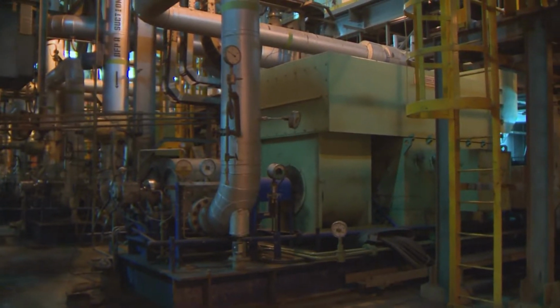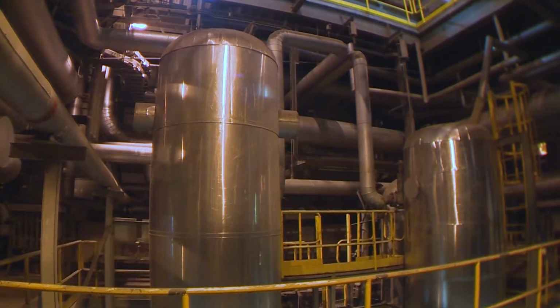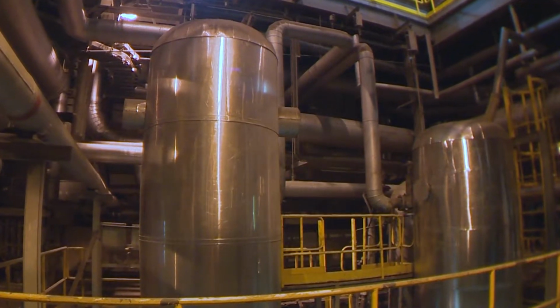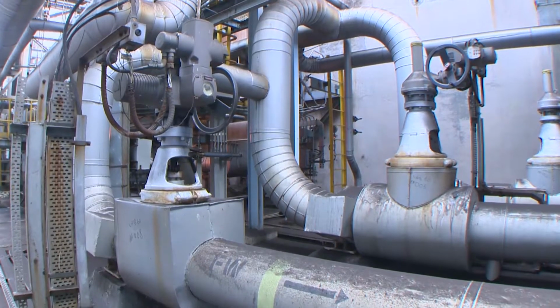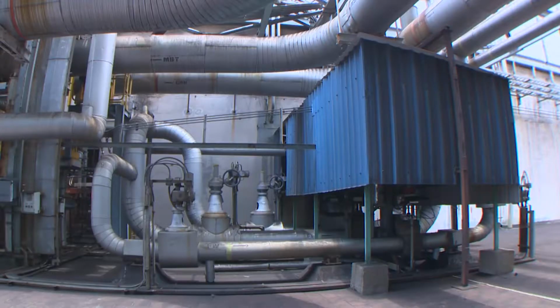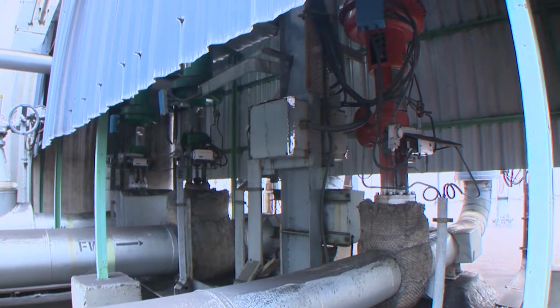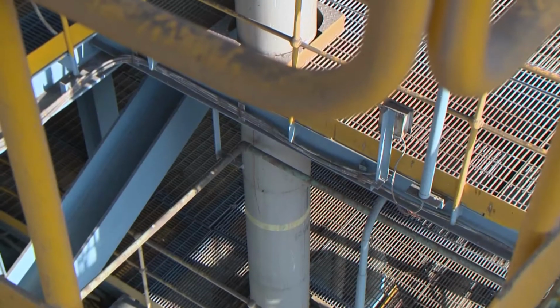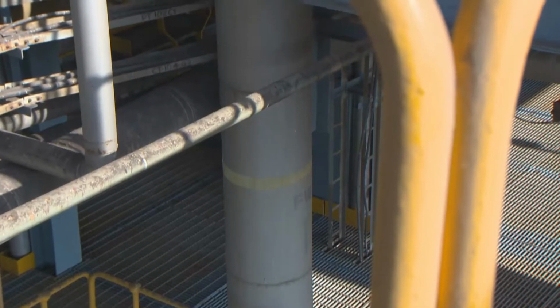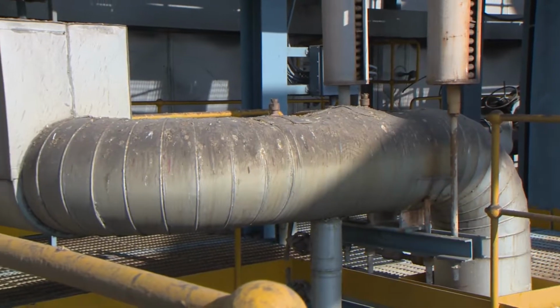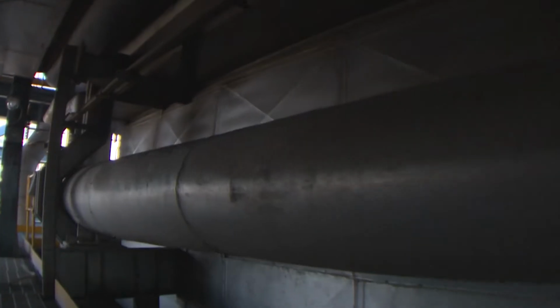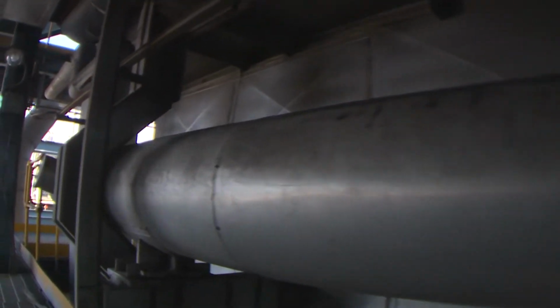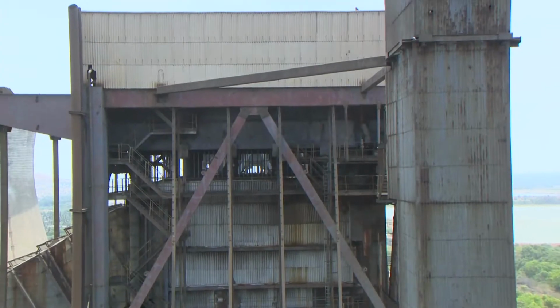Boiler feed pump supplies feed water to the boiler through high-pressure heaters with sufficient pressure and temperature. The feed water flow is regulated by pneumatically operated automatic control valves. Then the feed water goes to the economizer, which improves the boiler efficiency by extracting heat from exit flue gas and thereby increases the feed water temperature. The water heated in the economizer is sent to the boiler drum, which is located at the top of the boiler structure.